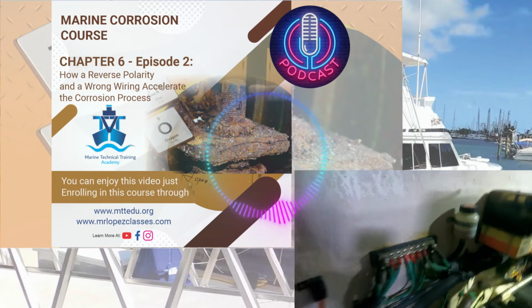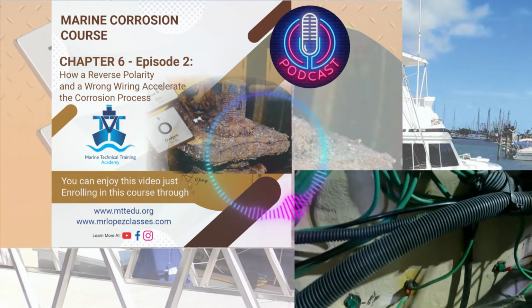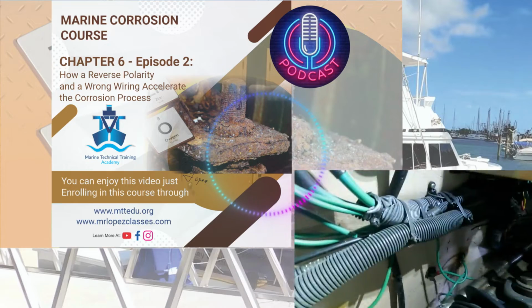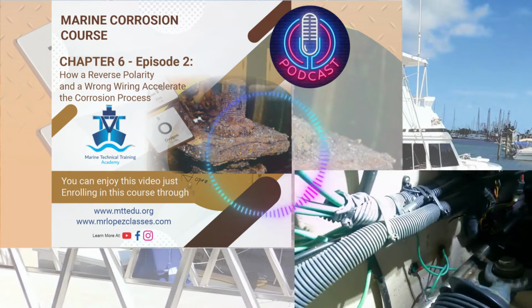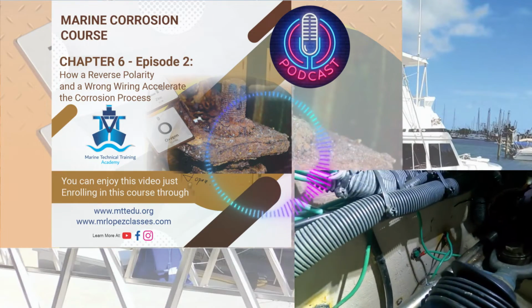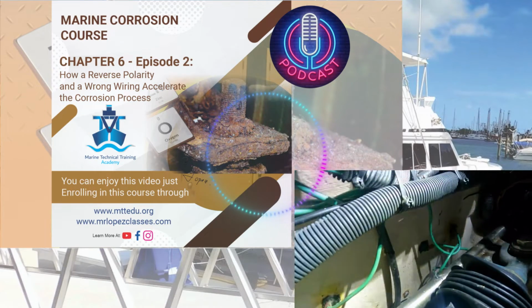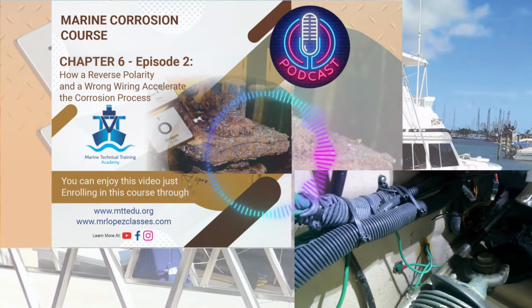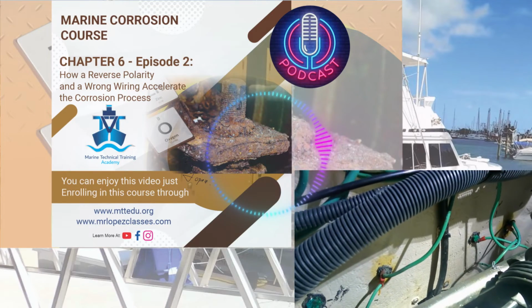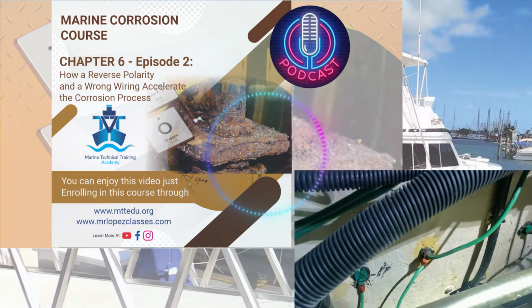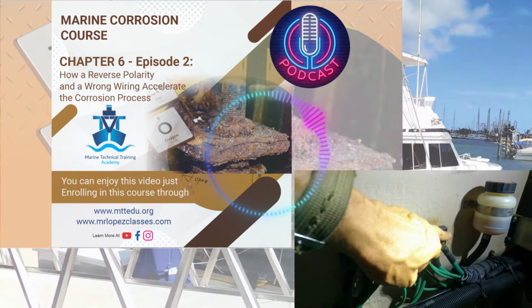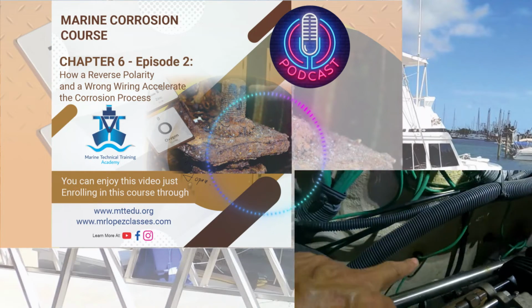You remember that situation? You have a switch, the hot and the neutral. And now the neutral bus bar is hot. The neutral bus bar is hot, and the breakers now interrupt the neutral, not the hot, because you switched those wires.